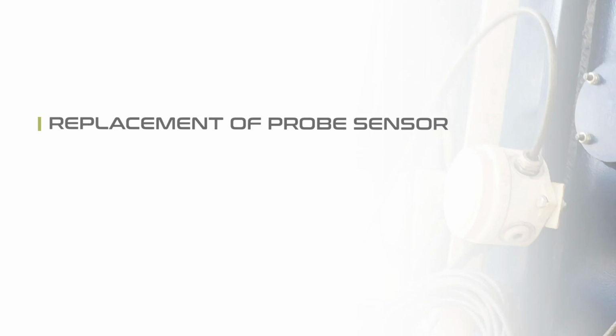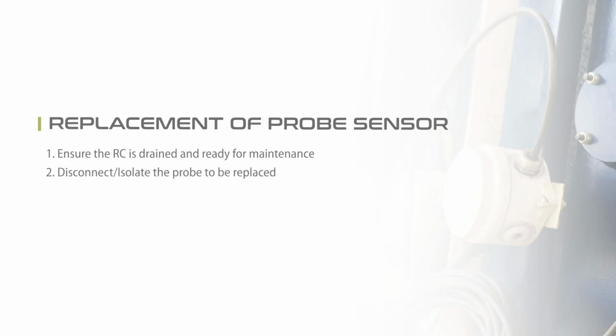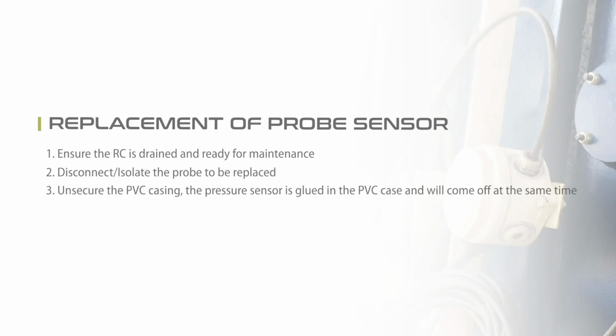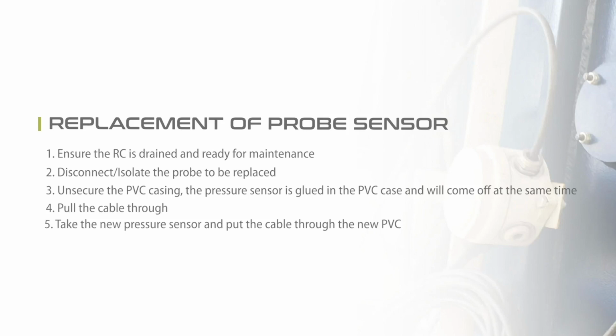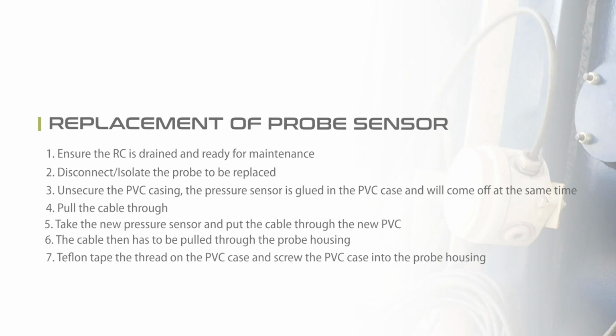Preventative maintenance. Replacement of the probe sensor. Ensure the reflux classifier is drained and ready for maintenance. Disconnect or isolate the probe to be replaced. Unsecure the PVC casing. The pressure sensor is glued to the PVC case and will come off at the same time. Pull the cable through. Take the new pressure sensor and put the cable through the new PVC. The cable then has to be pulled through the probe housing. Teflon tape the thread of the PVC case and screw the PVC case into the probe housing. Use Sikaflex to glue the pressure sensor into the PVC case.